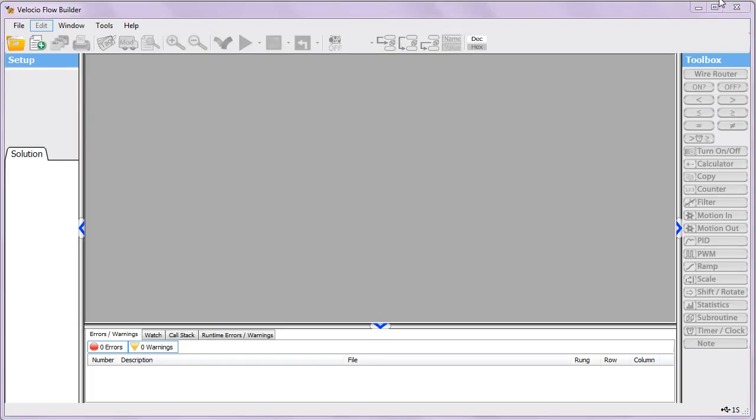Okay, we're going to go through the real-time clock functionality on the PLCs. And the first thing to know there is that while the PLCs will keep track of time for you, and you can do comparisons against it, that sort of thing, the PLCs themselves don't have a battery inside them. So most of the time, you want to make sure that you've got a battery somewhere in your power loop.